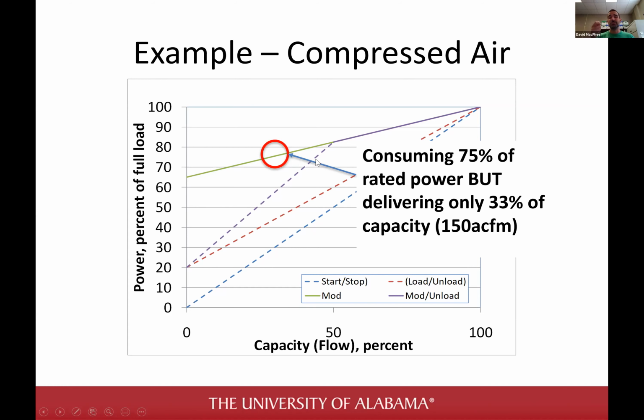In those ones, you can actually choose modulation with unloading, load, unload, or pure modulation. But I have been in a plant before where they've been very lightly loaded, and they're using a modulating control strategy where they had the option literally on the control panel to use load, unload. So that's kind of what this example is designed to represent. So let me get back to what I was saying before. 75% of rated power you've measured, it's only delivering 33% of capacity. So your facility's on average drawing 150 cubic feet per minute, which is 1/3 of the amount that this compressor can deliver, which is fine.